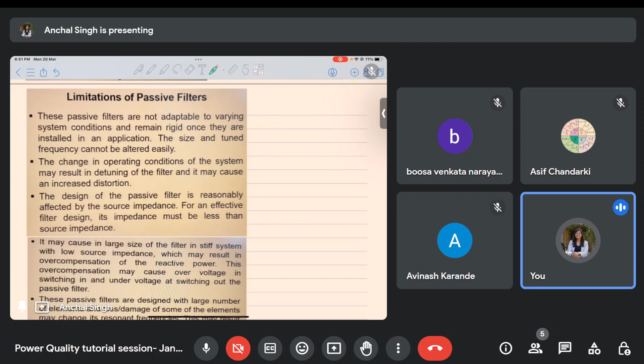And the design of the passive filter is reasonably affected by the design of source impedance. So if I am able to effectively estimate the source impedance of my system, then it is good. But if I am not able to do that, then it will be a problem, because we have a huge electrical network and it's difficult to accurately measure the source impedance in real time scenarios. Then another problem is because of the presence of fixed compensation, the size of the filter might be very high. The energy density is not that good for passive filters.